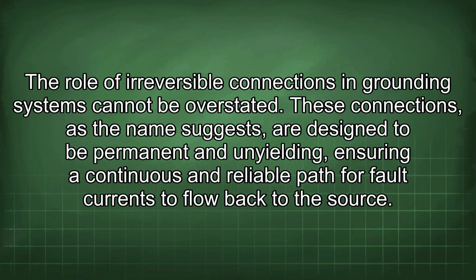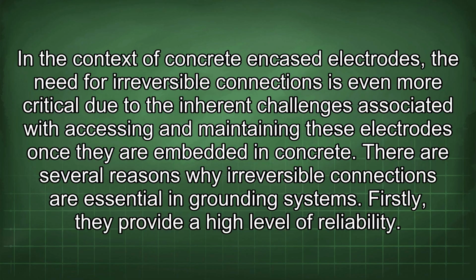The role of irreversible connections in grounding systems cannot be overstated. These connections, as the name suggests, are designed to be permanent and unyielding, ensuring a continuous and reliable path for fault currents to flow back to the source. In the context of concrete encased electrodes, the need for irreversible connections is even more critical due to the inherent challenges associated with accessing and maintaining these electrodes once they are embedded in concrete.